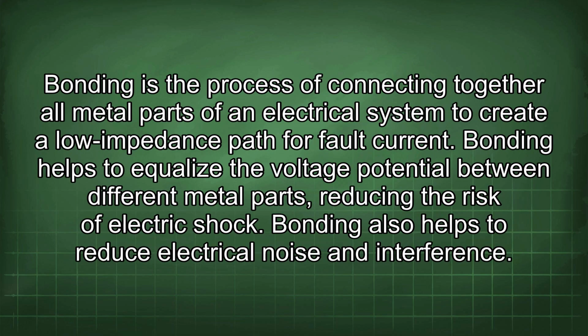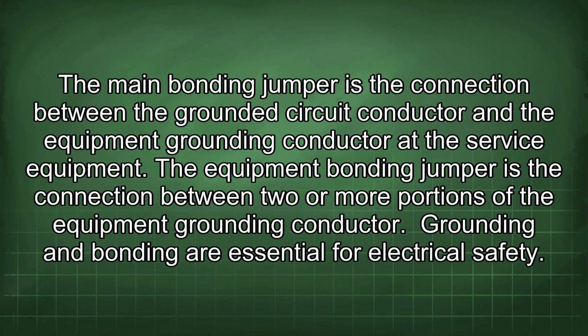Bonding is the process of connecting together all metal parts of an electrical system to create a low-impedance path for fault current. Bonding helps to equalize the voltage potential between different metal parts, reducing the risk of electric shock. Bonding also helps to reduce electrical noise and interference. The main bonding jumper is the connection between the grounded circuit conductor and the equipment grounding conductor at the service equipment. The equipment bonding jumper is the connection between two or more portions of the equipment grounding conductor.